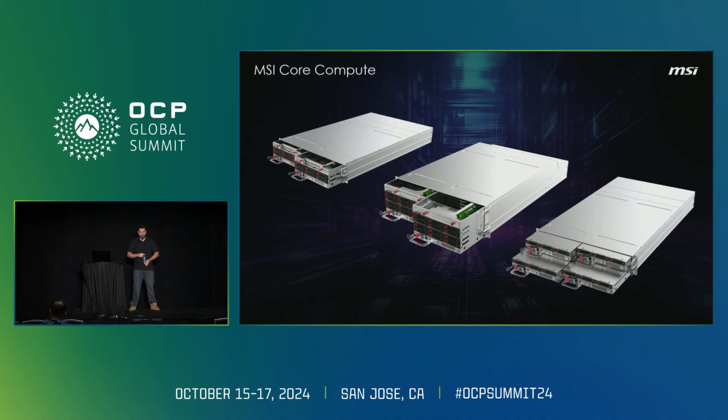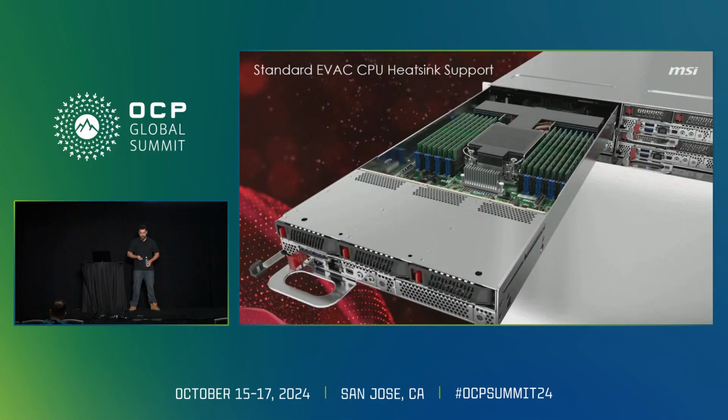And we're seeing fan power consumption numbers in a compute node configuration with node drive bays of around 30 watts per node. So it's very efficient once you scale up to the 3U2 node chassis. And the way we've done this is that we've architected our entire chassis. My entire roadmap is using what's known as an extended volume air cooler, or EVAC.